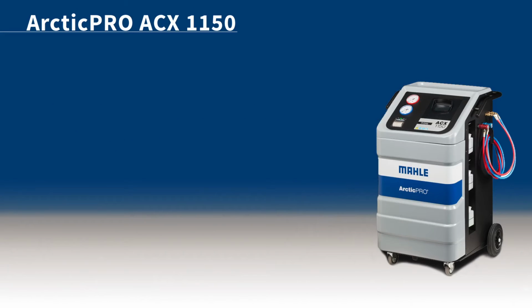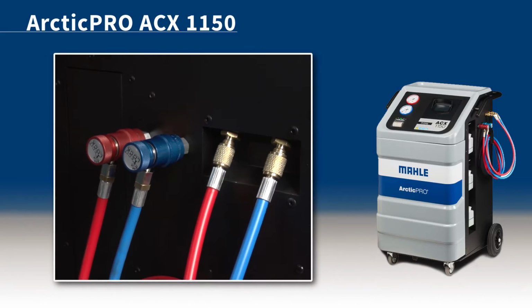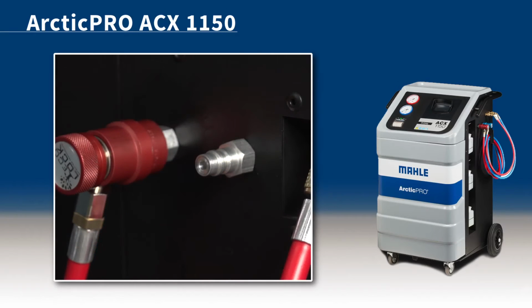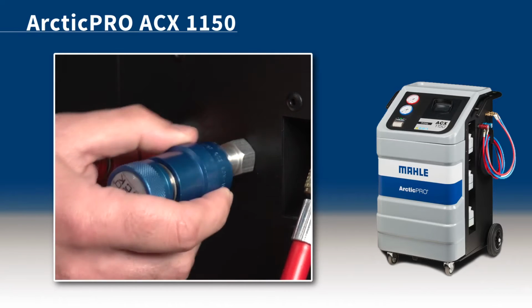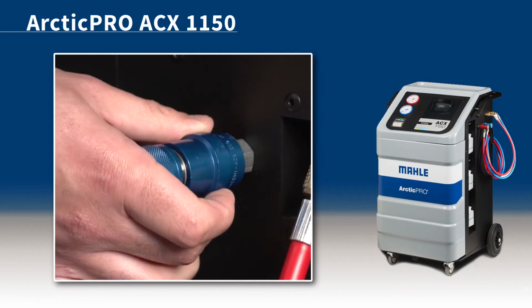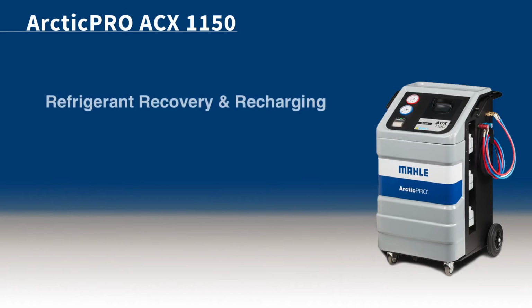A key feature of the ACX1150 and 1150H is the EcoLock quick couplers that enable the reduction of non-condensable gases formed inside the cylinder. They avoid the loss of refrigerant into the air during disconnections. To connect the coupling, position the coupling on the parking coupler and pull back the knurled section of the coupling element and press carefully onto the connections. The following functions will be reviewed: refrigerant recovery and recharging, vacuum generation, flushing.